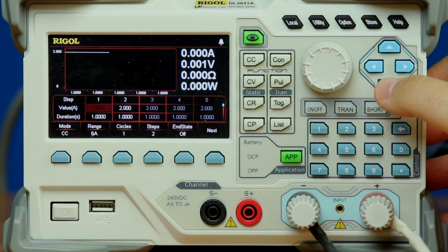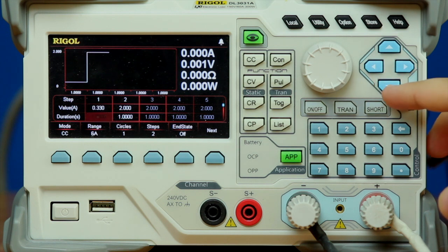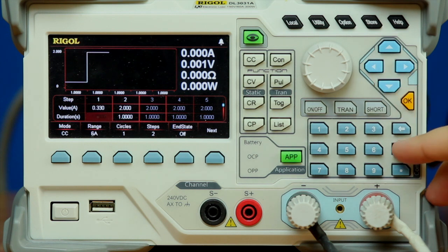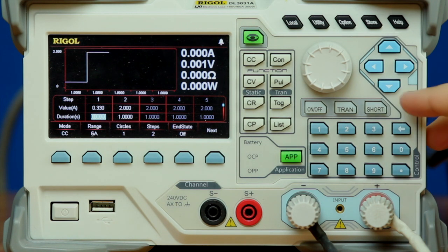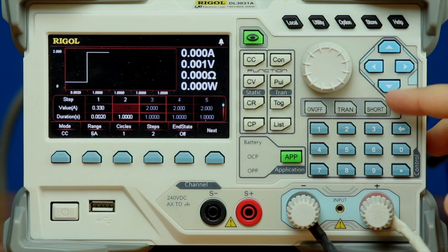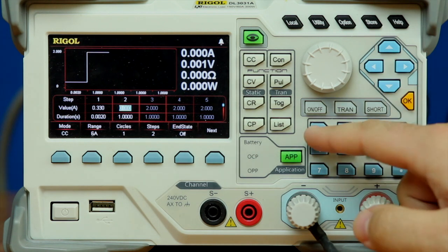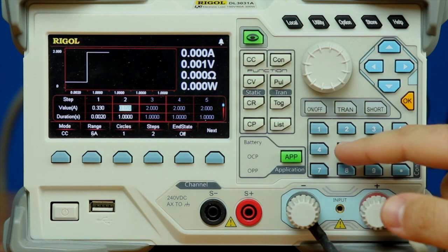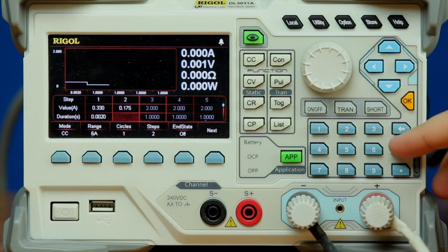And then I'll set the time duration to be at 0.002 seconds. And then the same thing for our low level, which will be 0.175 amps. And our time will be 0.1 second.